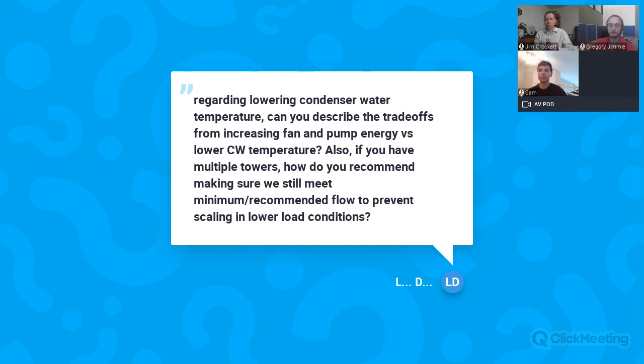So basically what we will usually do is pick a spot around 80%. We'll ramp the cooling tower fans up until they're running at 80% speed, and then we'll let the temperature rise until it's a cap and release type of approach. So we're trying to avoid running the towers at 100%. By the time you get them down to 80%, you've cut their power in half.